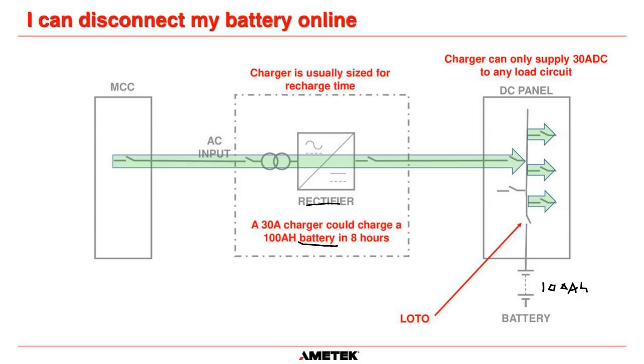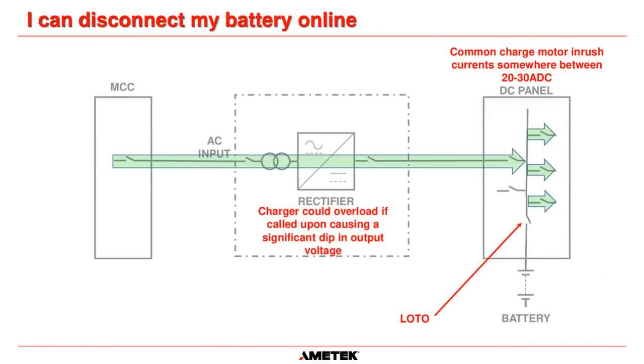But that doesn't mean that you can't connect maybe 100 amps of load to your system. And it depends on what kind of load you have. In most circumstances, once again, in a switchgear charger, you're going to have tripping and closing coils, and they're not constantly on. So a load profile has to be designed by the engineer. But in many cases, your load circuits are going to see far more current than the charger itself can actually supply, because that's not what the design of the charger is for.